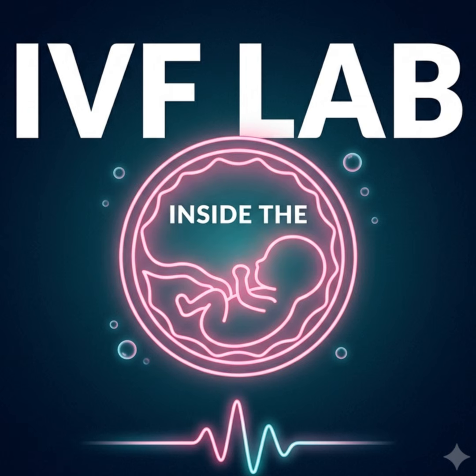Precisely. And then consider the laser path. The infrared laser fires down through the optical column, bouncing off precisely angled dichroic mirrors before passing through the objective lens. Even a minor physical bump to the massive microscope frame, say, someone moving the desk slightly during cleaning, could induce a microscopic alignment drift in those internal mirrors. Oh. The embryologist might look through the binocular eyepiece, align the digital targeting reticle perfectly over the zona pellucida, and fire the laser. But because the internal mirror shifted, the actual physical beam of light might strike 2 microns to the left of the crosshairs, striking the living cell instead of the protective shell. That is a terrifying prospect.